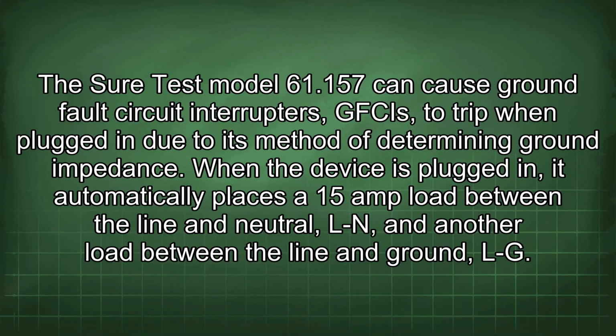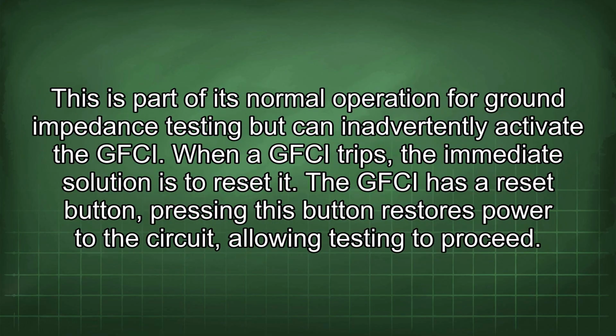The Sure Test Model 61.157 can cause ground fault circuit interrupters, GFCIs, to trip when plugged in due to its method of determining ground impedance. When the device is plugged in, it automatically places a 15-amp load between the line and neutral, LN, and another load between the line and ground, LG. This is part of its normal operation for ground impedance testing, but can inadvertently activate the GFCI.